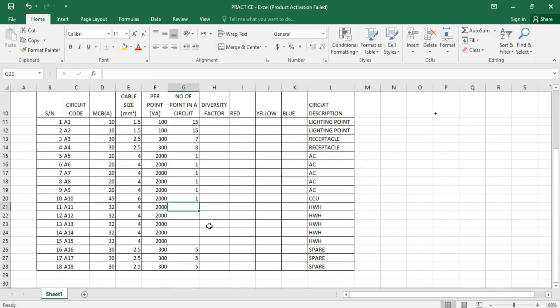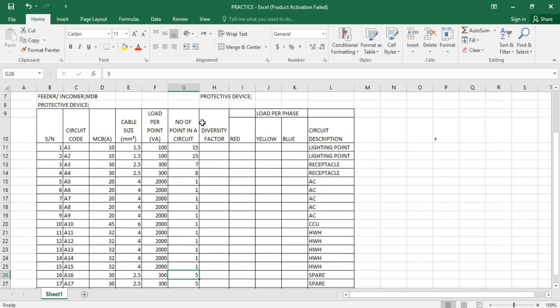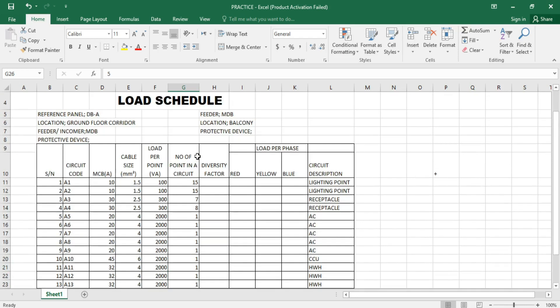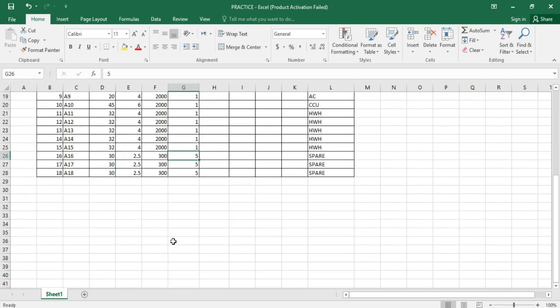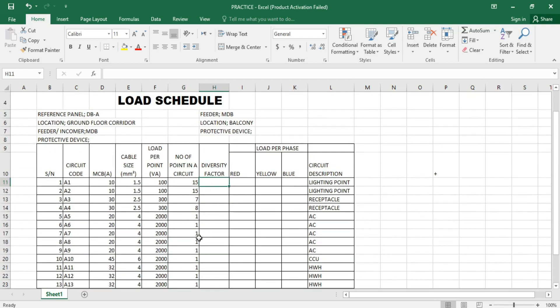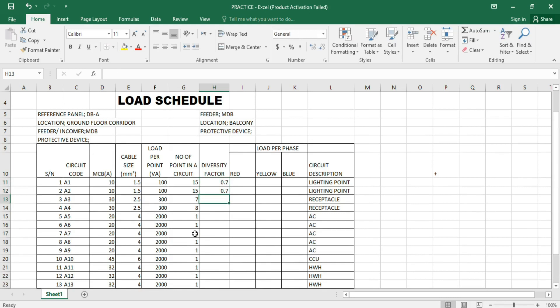We'll be having one throughout here. The next column is the diversity factor. As I explained in our last class, especially circuits with high numbers of fixtures — not all these fixtures will be energized at the same time. As we're having 15 fixtures here, probably only 10 will be energized simultaneously. We have a table recommended by NEC for this, but for our project design let's choose the standard: 0.75 or 0.7 for lighting, and 0.9 for the ring circuit.